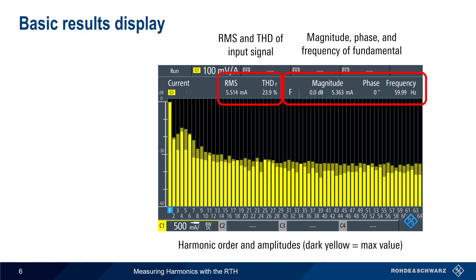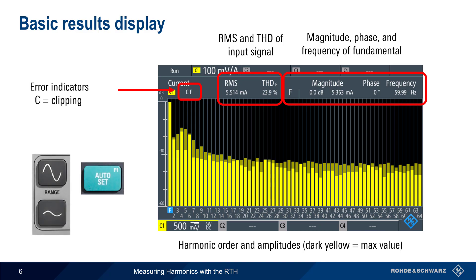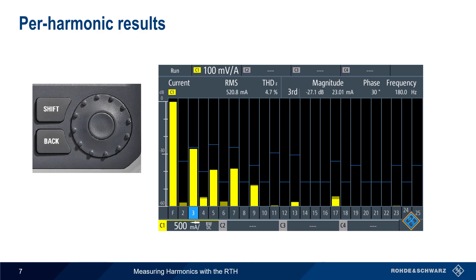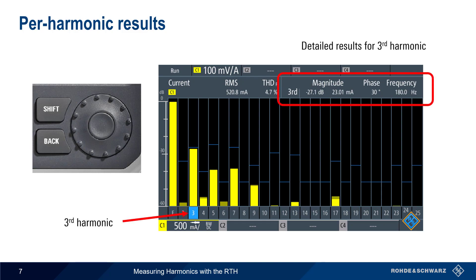Invalid measurement results are shown using two types of error indicators: C and F. C means that clipping is occurring, and this can be corrected using the range keys or the autoset function. F means that the fundamental frequency was not properly detected, in which case the user should manually set the fundamental frequency of the input signal. The rotary knob on the front of the RTH can be used to select each individual harmonic to obtain magnitude, frequency, and phase information for that specific harmonic. For example, here we've selected the third harmonic, highlighted in blue, and the RTH displays the values of magnitude, phase, and frequency for this specific harmonic.